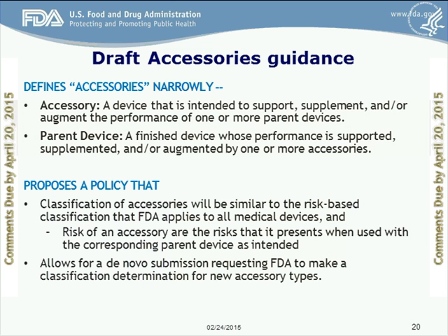As you can see on the slide, CDRH defines accessories as devices intended to support, supplement, or augment the performance of one or more parent devices. In brief, the device supports the performance of the parent device by enabling or facilitating that device to perform according to its intended use. The device supplements the performance of the parent device if it adds a new function or a new way of using the parent device without changing its intended use.